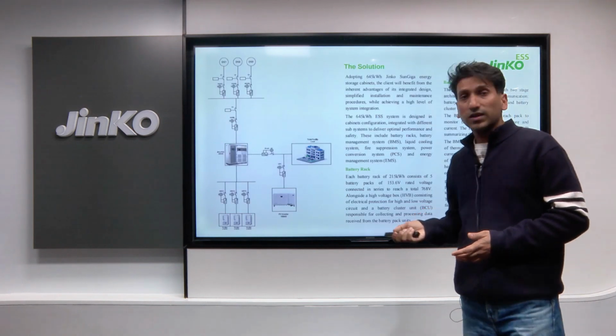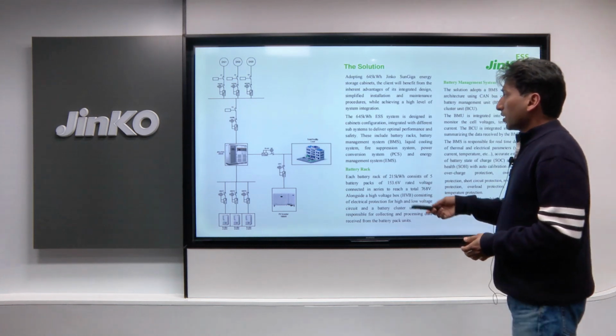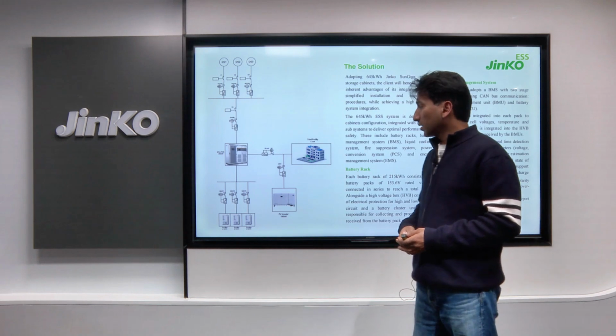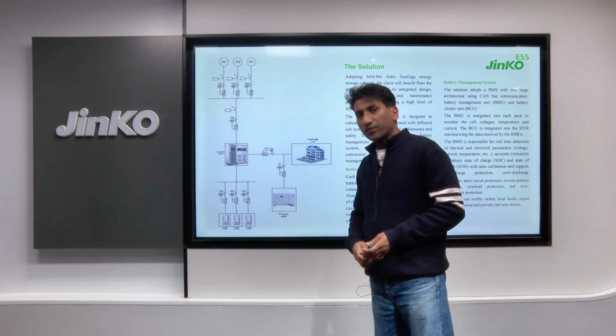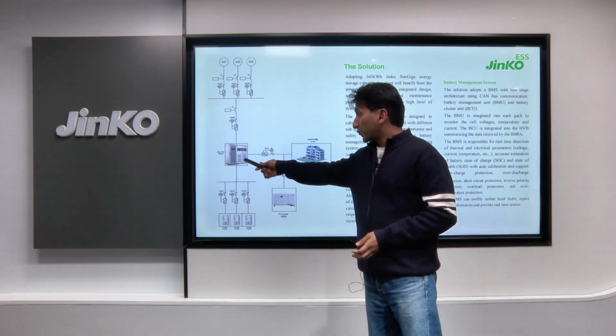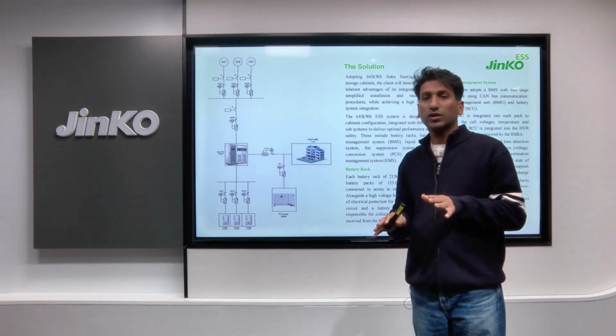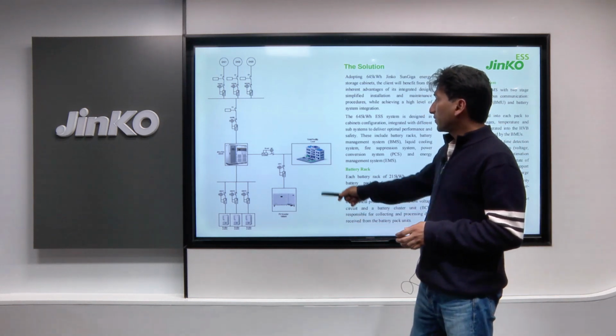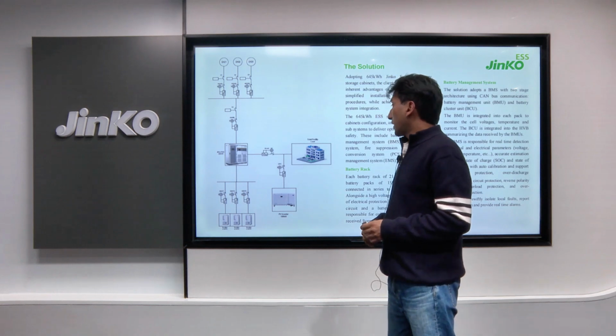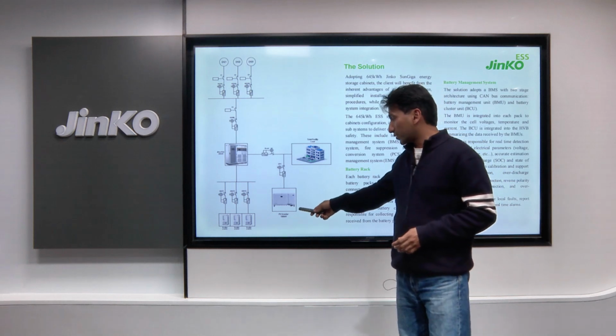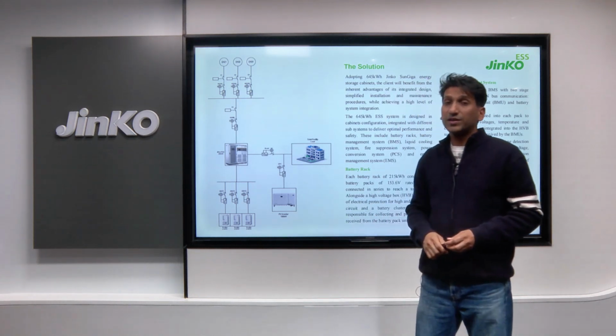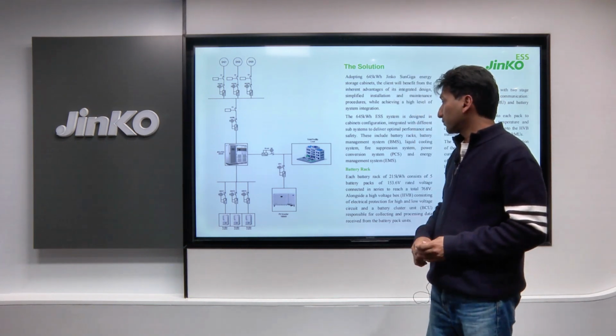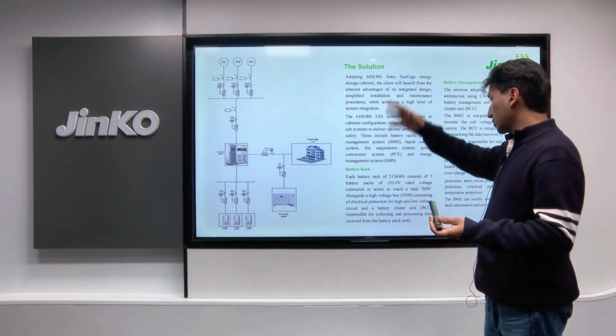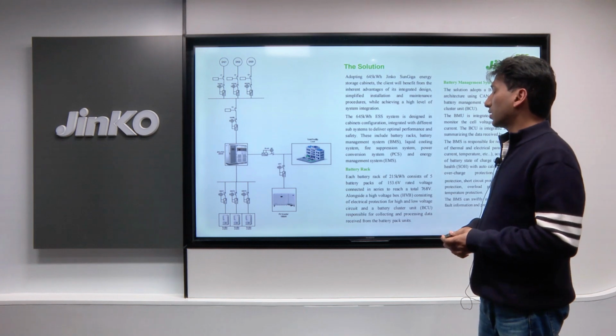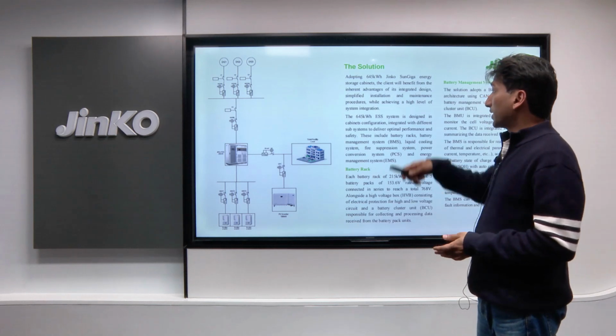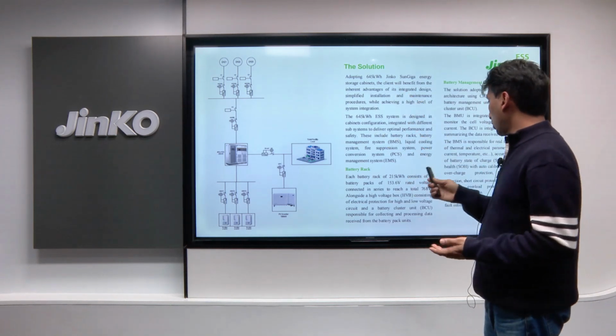As you can see from this slide, this is the SLD, the single line diagram, for the site. We have connected 3 SunGiga of 215 kilowatt hour to the PCS of 250 kilowatt. This PCS can work in both on-grid and off-grid mode. Then it's connected to the diesel generator, which was already on the site, and to the PV inverters. This PV inverter is 180 kilowatt, the maximum power it can supply. This is the whole solution with 3 SunGiga, a 250 kilowatt PCS, a 180 kilowatt PV inverter, and the diesel generators, supplying power to the load.